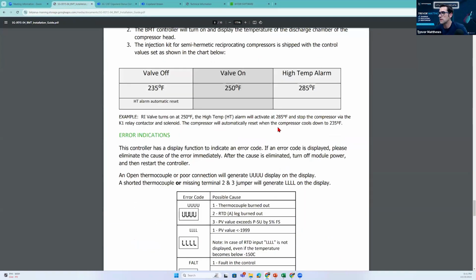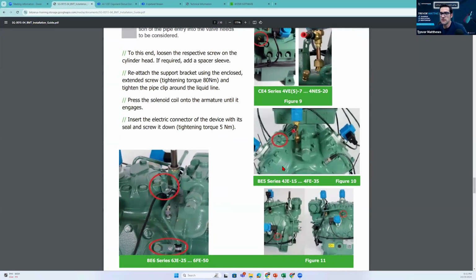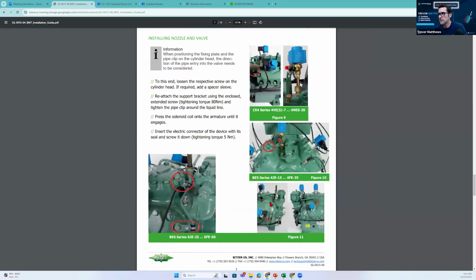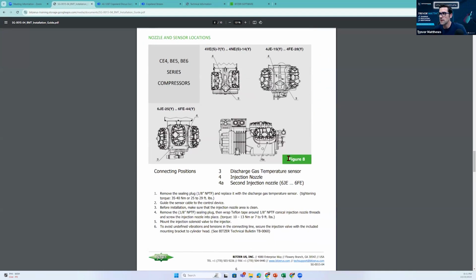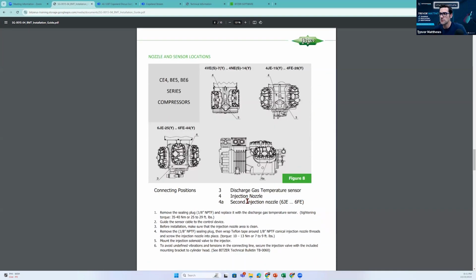Kind of like when I go to the Bitzer one right here. If I zoom out a little bit, you see this is a 6-cylinder. Do you see how it's piped? You have to have two different injection valves and two different temperature probes. And right here, it'll show you where the injection nozzle goes. And sometimes you have a second injection nozzle on the Bitzer one. So right here on this side there would be a nozzle, and then a nozzle on this side for that injection.